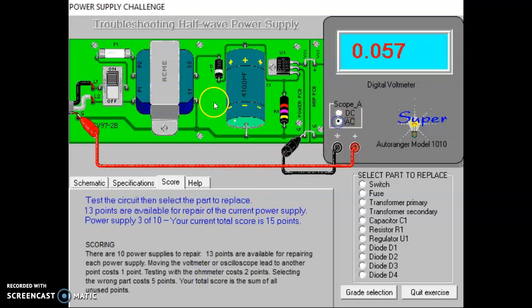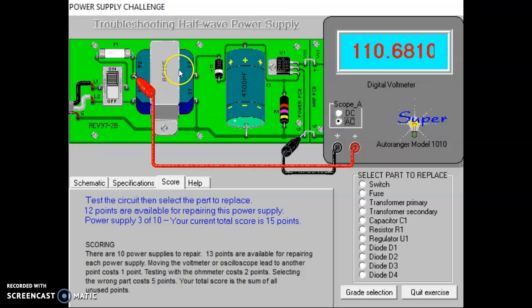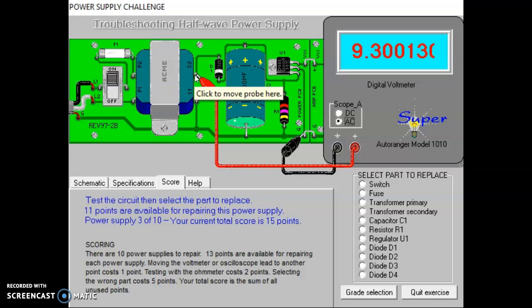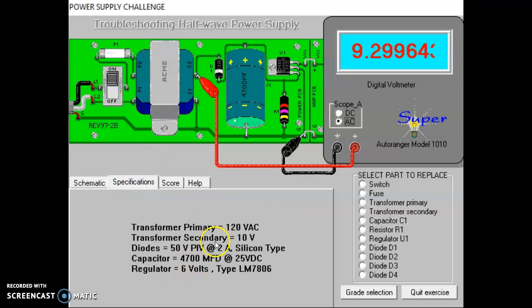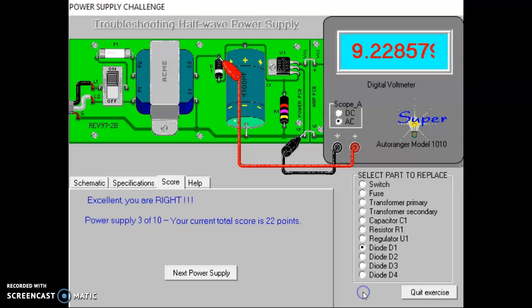So we start with an AC sense. Let's go to our primary - we got a good 110. Look at our secondary - we're good there. Let's take a look. We're going to have 6 volts on our voltage regulator input, and we got 0 volts on our voltage regulator output. So we look here, and we're at 0 volts coming into our voltage regulator. Let's step back a little bit - our diode is our issue. I didn't check that earlier, but diode 1 is going to be our problem, because on this side of the diode our secondary voltage is there, and then diode 1 has a 0. So grade that selection, we're good, we can move on from here.